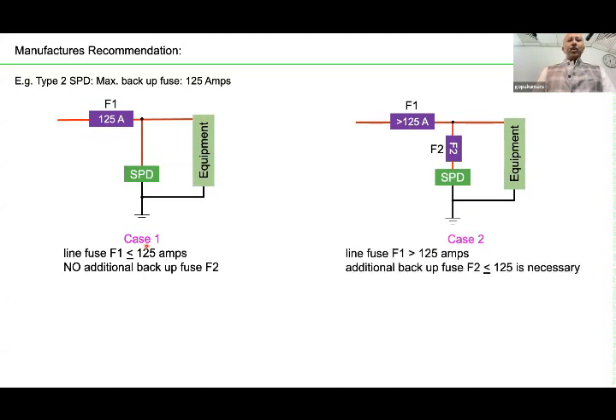And in case 1, you have, for example, F1 up to 125 amps, there is no backup fuse. If the fuse is more than 125 amps, there is an additional F2. This is how generally the installation is carried out, because the manufacturer told that up to 125 amps, you don't need a backup fuse.